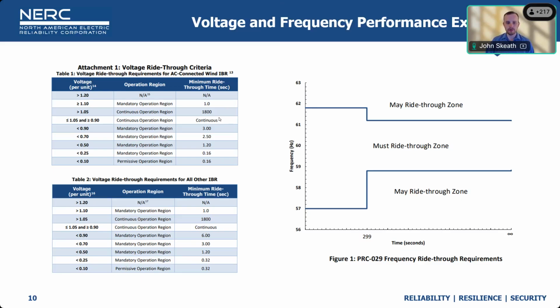in the voltage ride-through. However, you can see the only major difference between these two charts is going to be in the lower voltage limits, where you have the less than 90 or less than 0.9 per unit being roughly about half that of all other IBRs. But if you plot this on out, the only differences you'll see are under these very low and shallower voltage curves. But those are the curves in Attachment 1. Those specify the expectations measured at the high side of your main power transformer for the facility to ride through or to continue to exchange current during the disturbance.